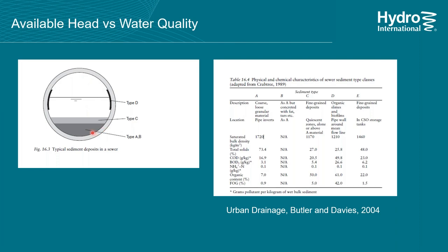And what they say is, the flow at the bottom of a drainage pipe is this kind of loose, coarse material. But when you get to the top of the pipe, yes, it's floatables and oils and things like that. And you might lose that when you bypass, but you're going to be sending most of your most polluted, heaviest sediment-laden flow to the treatment unit. So, if you don't have a lot of head on site, bypass can be considered a tool to allow you to keep some of your water quality goals while still maintaining usable head levels for your drainage system.